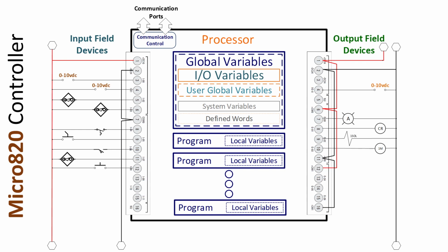For example, you could write a program for a conveyor. Let's say you have a conveyor system, you're sorting cartons onto spurs. And these spurs, you're going to sort products of the same type out onto a spur, and once you have enough to make a unit load, then you're going to push that on down to another trunk that's going to go to a unitizer, a palletizer, and make up a unit load of that particular product. And let's say that you have 10 conveyors, 10 spurs. You can perfect the program for one conveyor and then copy, paste it into another program. And the only change that you have to make with each additional program is any use of global variables, like I/O variables. Obviously, you can't use the same memory location for the same photo eye in all 10 conveyors.